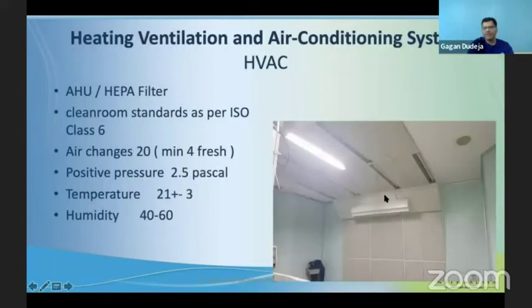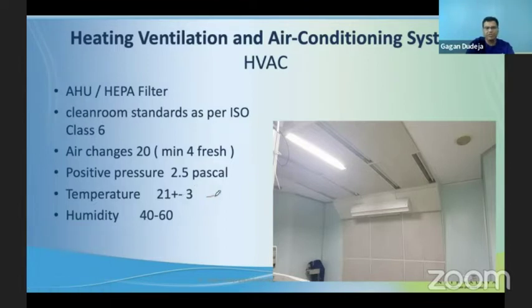If you don't put in an AHU or HVAC system, you may end up using split AC, but whenever you upgrade your OT, you should at least leave a provision for fitting a proper AHU or HVAC system. This helps maintain the OT to ISO Class 6 standard with proper air changes, lets you maintain a positive pressure of 2.5 pascals or higher, and lets you control the temperature within the desired range. All this comes with an HVAC or AHU system.